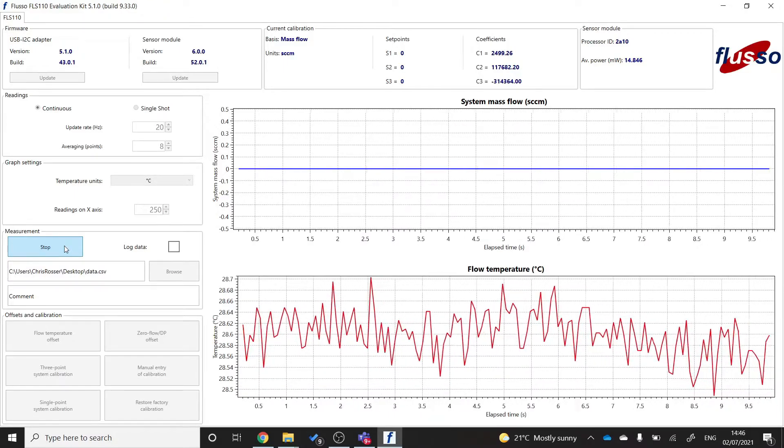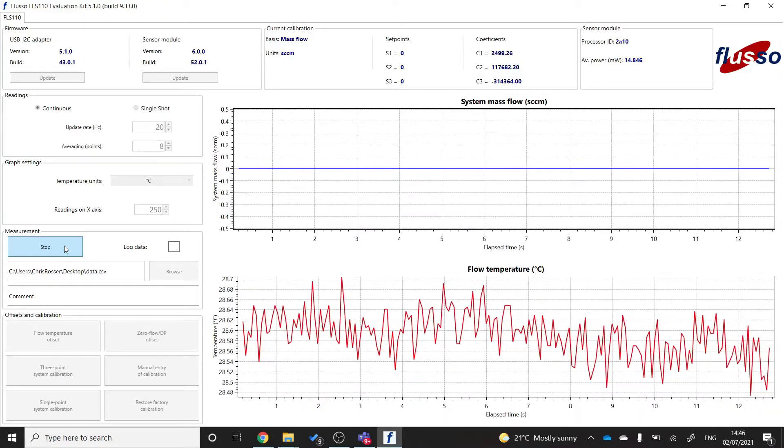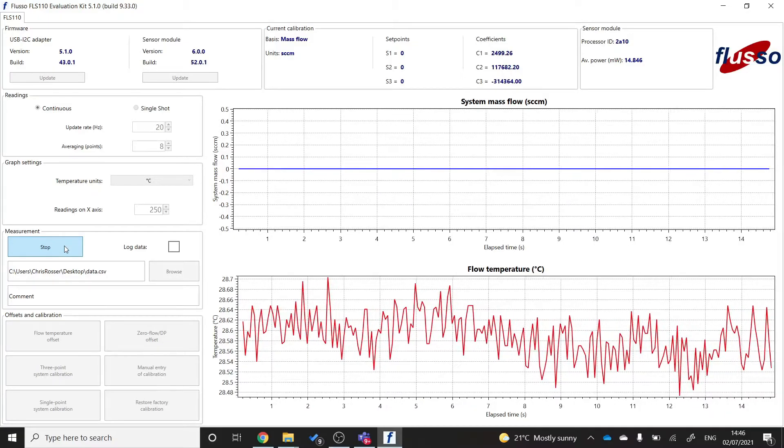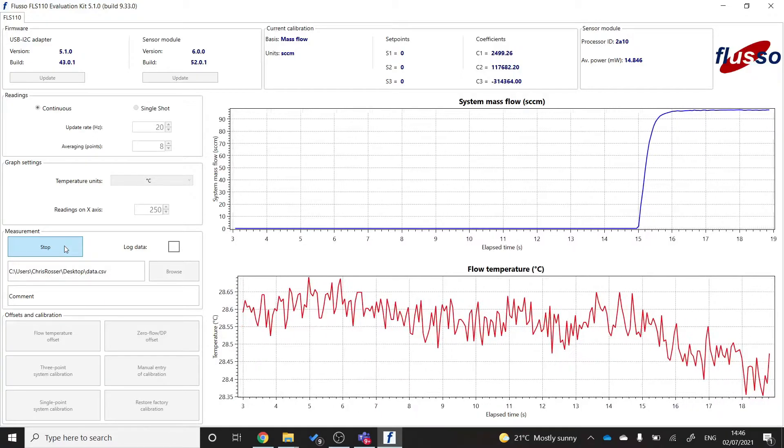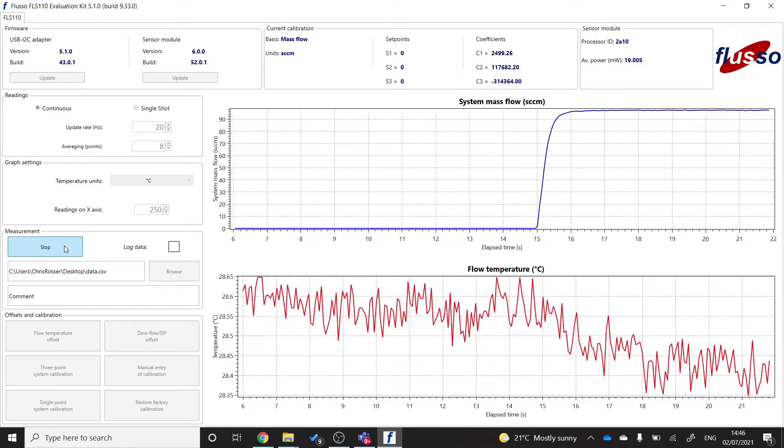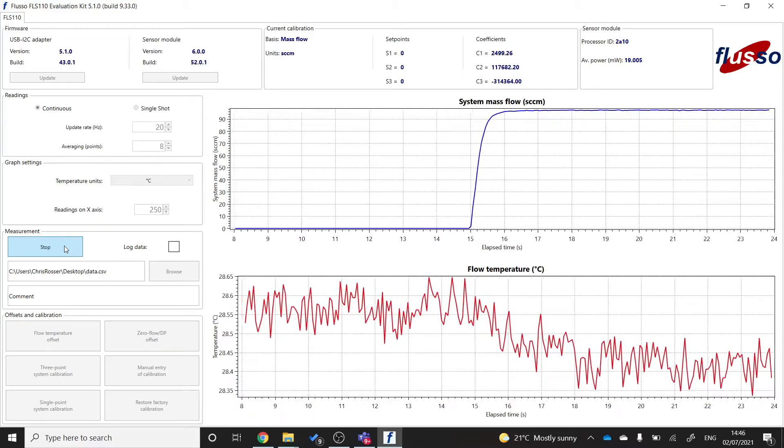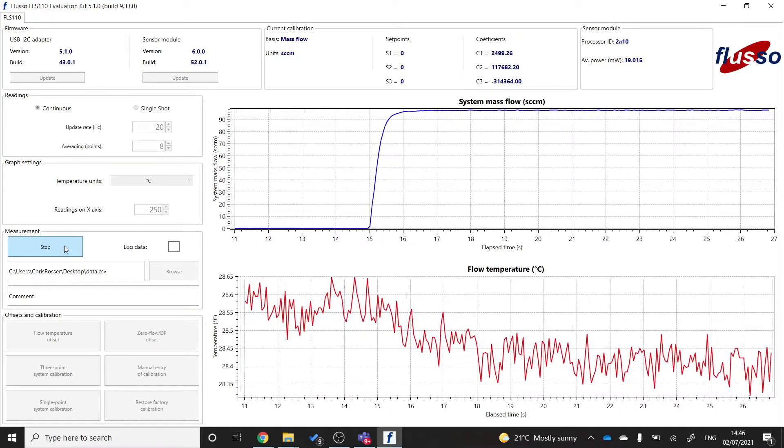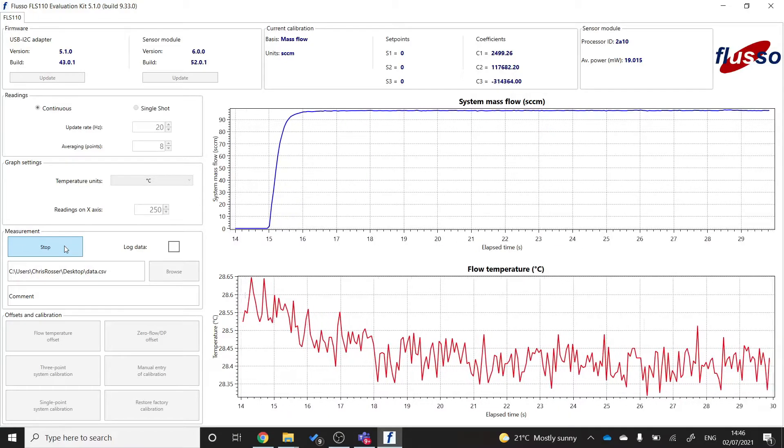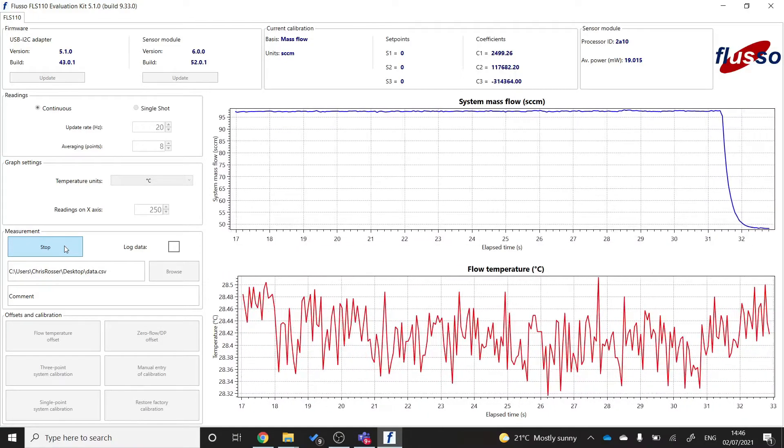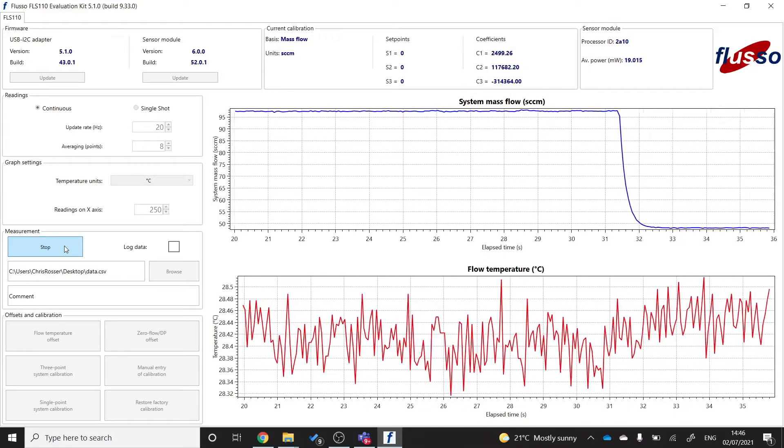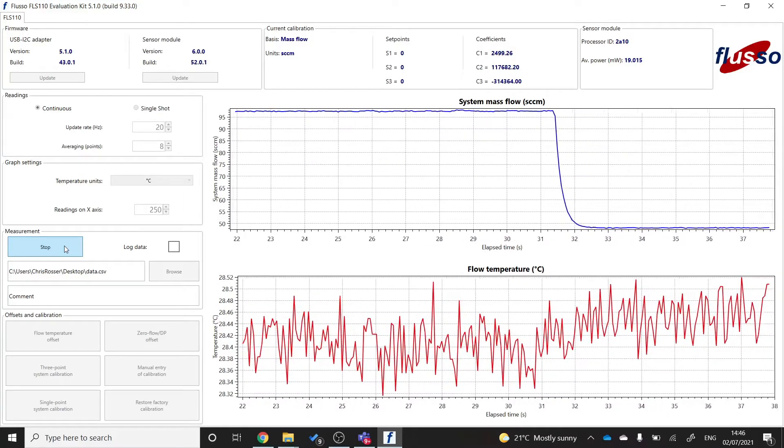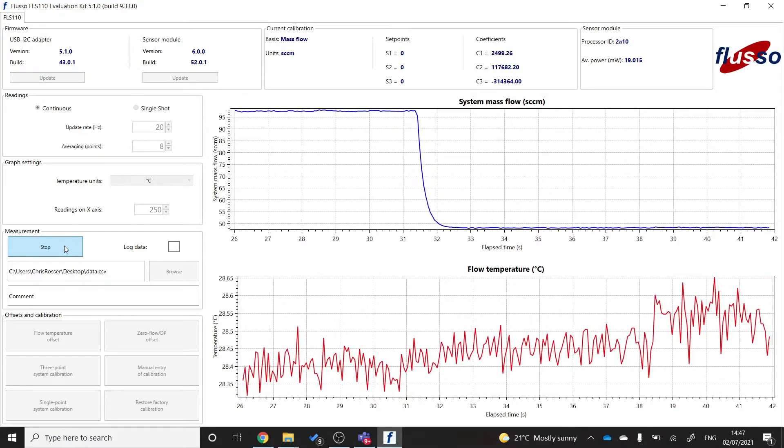If we now pass a flow through the sensor, I'll set this mass flow controller to 100 SCCM. You can see that the sensor begins to report 100 SCCM. And if I turn the flow down, let's say I turn it down to 50 SCCM. You can see that the sensor drops to 50 SCCM. So if it's all working like this, then you are set up and ready to measure flow.